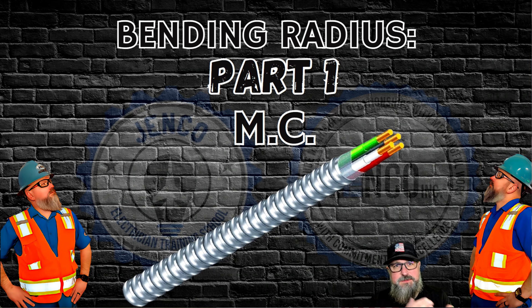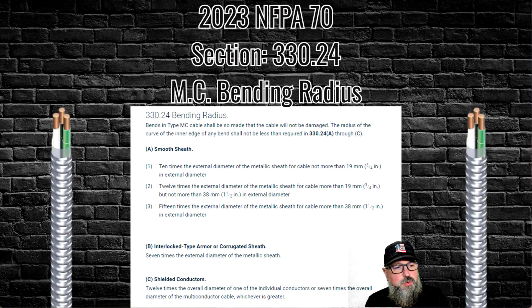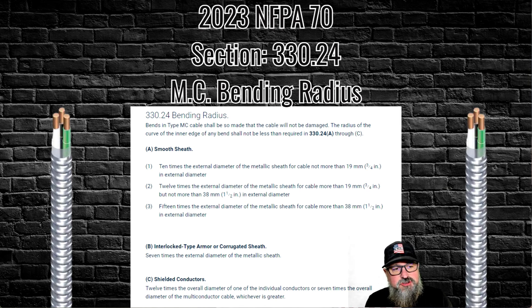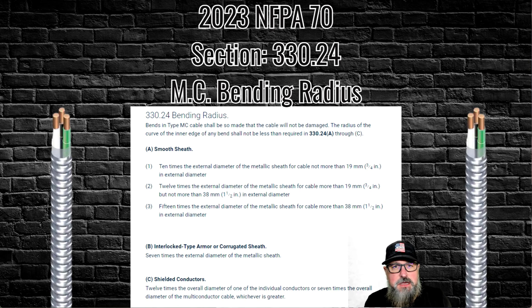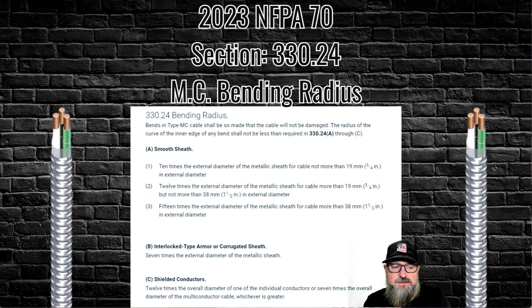This is going to be a two-parter — I'm splitting it up so you're not watching a 30–40 minute video. Part one is about MC. NEC 330.24 states: bends in type MC cable shall be made so that the cable will not be damaged. The radius of the curve of the inner edge of any bend shall not be less than required in 330.24 A through C. What we mostly deal with in the field is B — interlock type armor or corrugated sheath — which is seven times the external diameter of the metal sheath.